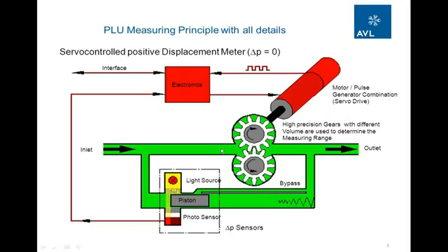This measuring principle is long time stable in calibration, and therefore we have 2 reasons. The first reason is, if the pressure drop here is on both sides the same, then these gears are pushed from all directions with the same power.